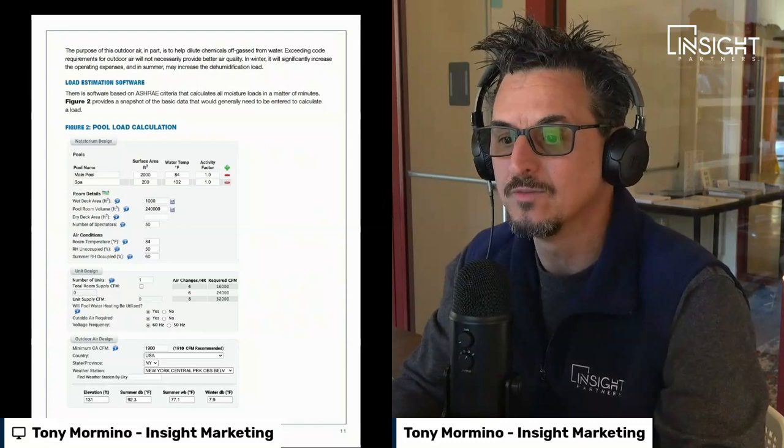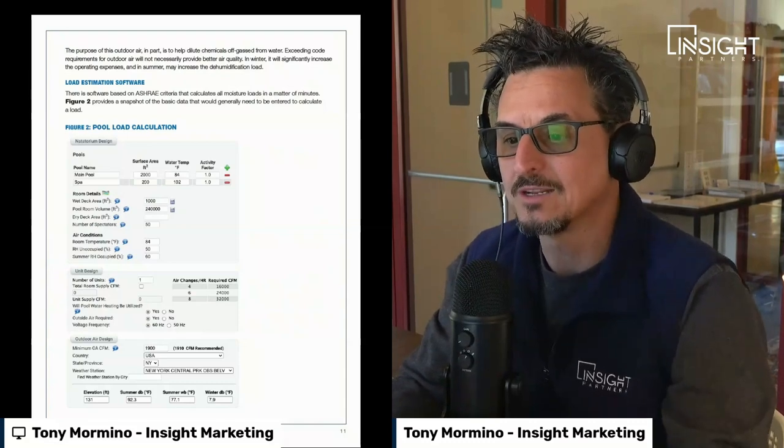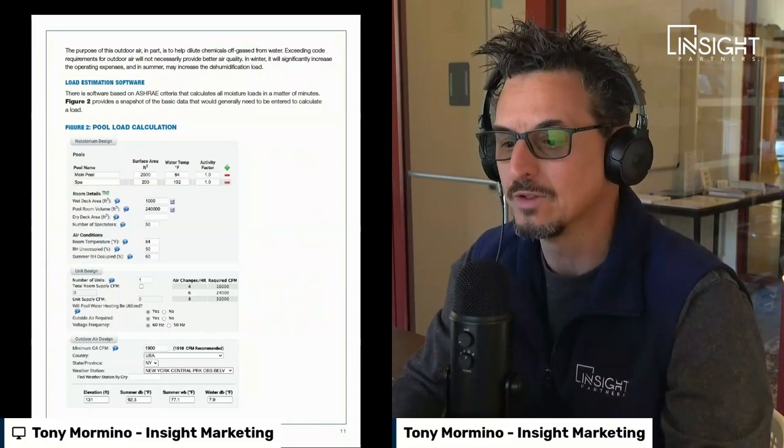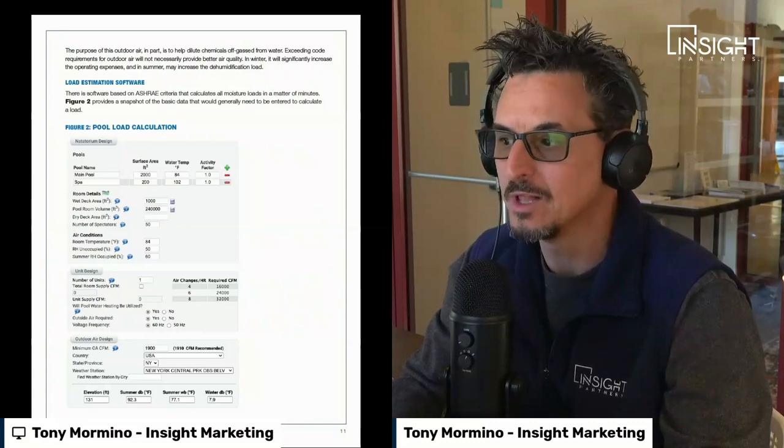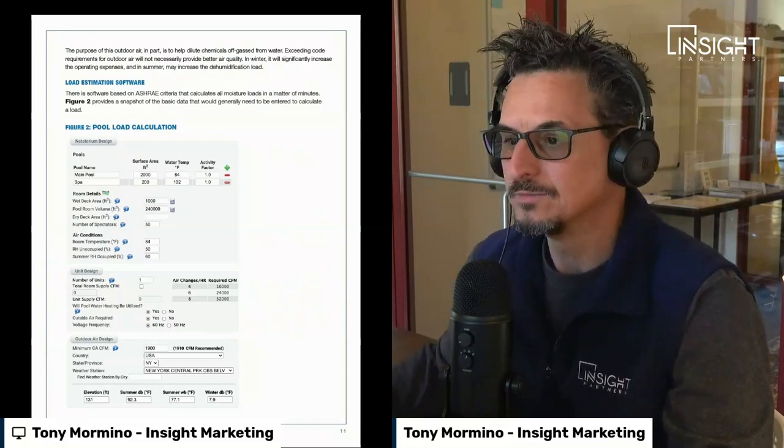The load estimation software asks for the main pool area, spa area if applicable, wetted deck area, pool room volume, number of spectators, desired room temperature conditions, desired water conditions, and location — and it will actually size the unit for you. So get with your local trusted pool representative. A few key notes on outdoor air: locate outdoor air intakes away from sources of airborne contaminants such as exhaust fans and plumbing vents; the outdoor air may need to be preheated to 65°F if more than 35% of total airflow is outdoor air or if the winter design temperature is below 10°F; and a certified air balancing contractor must balance the system airflow.